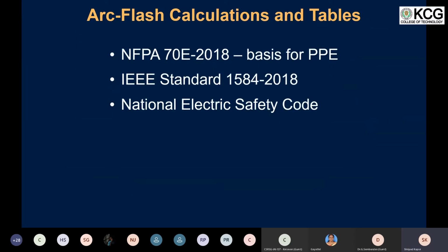So there are basically three standards that govern these kinds of arc flash hazards and the PPE requirements of arc flash. The NFPA 70E basically provides a basic idea of what the PPE should be, depending upon the amount of incident energy that is going to occur during an arc flash fault. And then there is IEEE standard 1584, which tells you how to calculate the incident energy and the boundary of an arc flash if the arc flash were to happen.